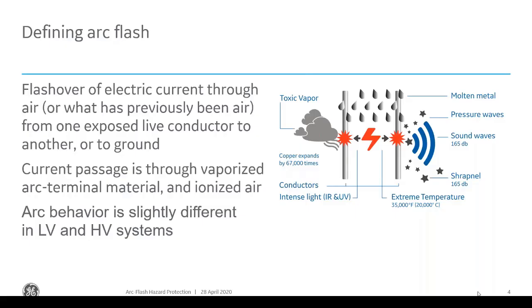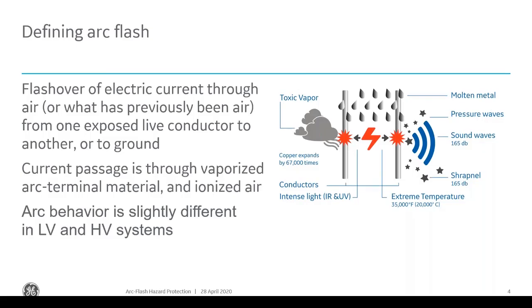The resulting hazards that it creates are intense light in the IR and UV spectrums, and extreme temperatures up to 35,000 degrees Fahrenheit, which can obviously cause metals to melt, to bend, to deteriorate, which then can cause toxic vapors to be let out from these vaporizing materials, such as copper. And because of the expansion of these materials, it causes sound waves and pressure waves, which can then cause shrapnel to be thrown about at high speed, which can be very hazardous for personnel.